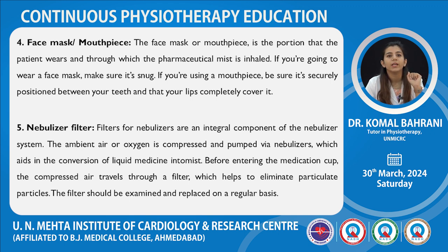Now fifth is the nebulizer filter. Filters for nebulizers are an integral component of the nebulizer system. The ambient air or oxygen is compressed and pumped via nebulizers, which aids in the conversion of liquid medication into mist. Before entering the medication cup, the compressed air travels through the filter, which helps to eliminate particulate matter. The filter should be examined and replaced on a regular basis.